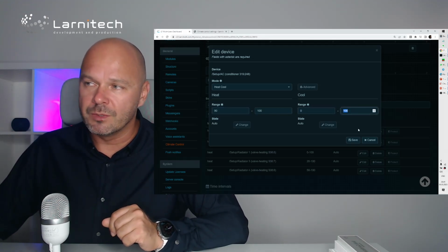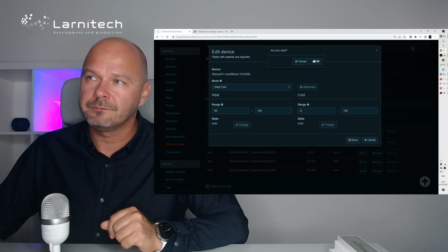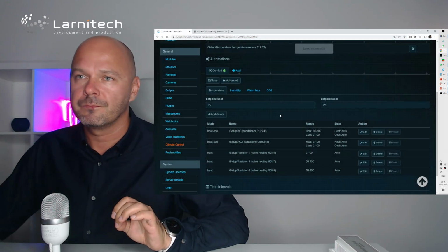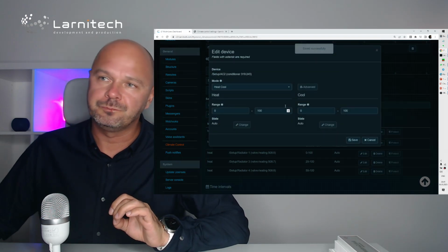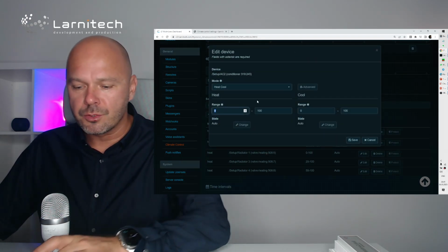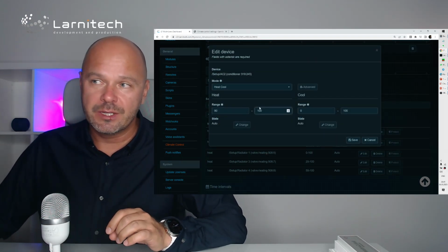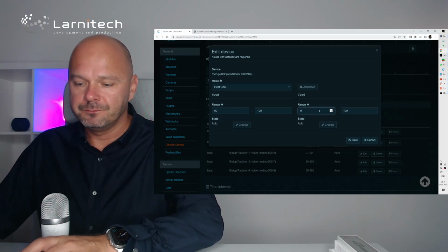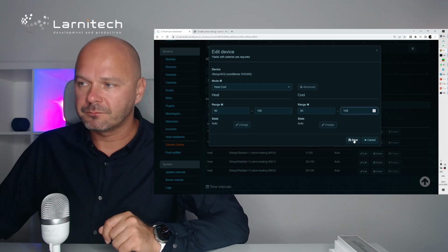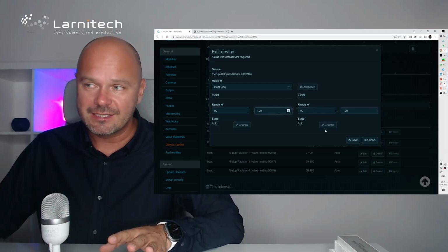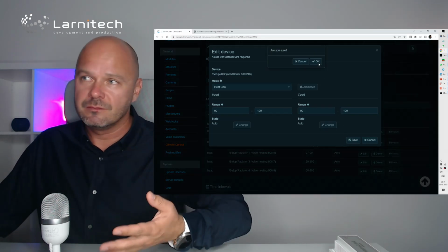And cool will be 0-100. And the second AC will also work 90 to 100 for heating and 90 to 100 for cooling. So only if a lot of cooling or a lot of heating, then it will start working.